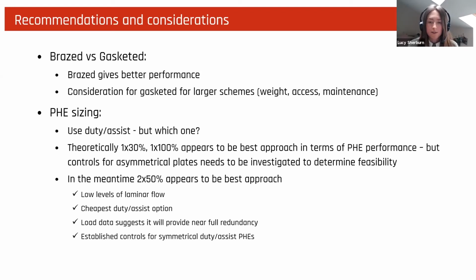So the duty assist at 250. This provided you with pretty low levels of laminar flow. It was ever so slightly the cheapest duty assist option. The load data suggests it will provide near enough full redundancy, and we have established control methods for symmetrical duty assist plate heat exchangers. Should note that this is quite high level, and there are many project specifics that you should consider when choosing your plate sizes and what type of plate. And control valve selection will play a major part in getting those stable temperatures, which Dan was talking about at the start. So that is still a major consideration.